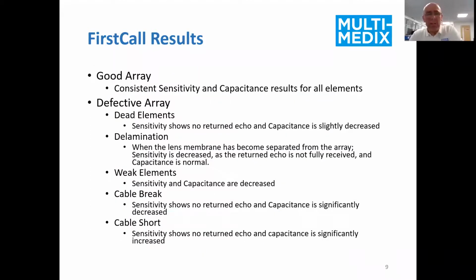So in summary, a good array would have good sensitivity and capacitance across all of the elements. However, some level of defect would show as dead elements, where we've got no sensitivity and only a slight reduction in capacitance; delamination, where we've got a reduction in sensitivity but a normal capacitance; weakened elements, where sensitivity and capacitance are both decreased; cable breaks, where we have no echo, so no sensitivity, and a significant drop in capacitance; and a cable short, where we see a spike in capacitance but no sensitivity in the echo.